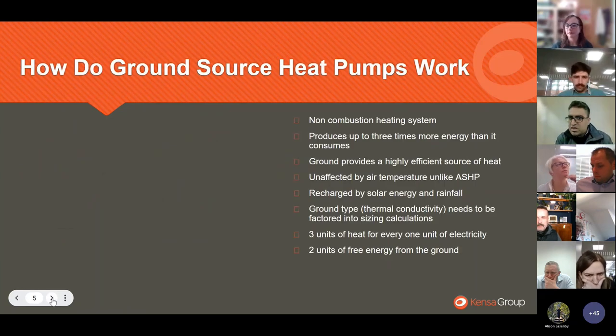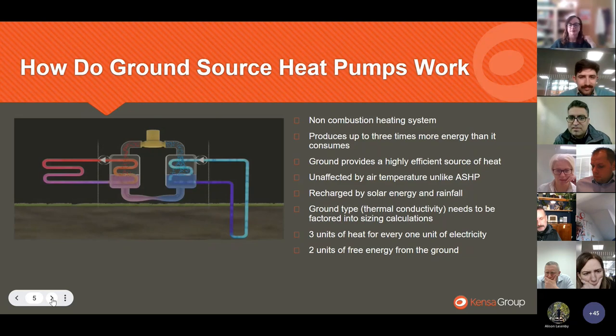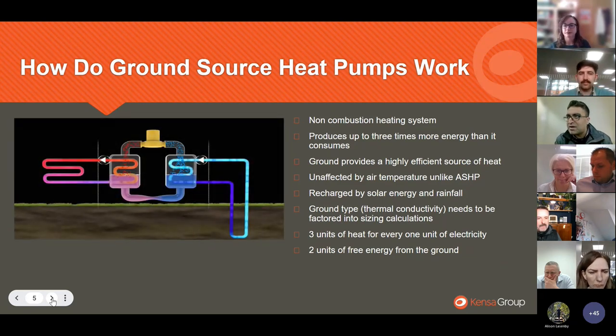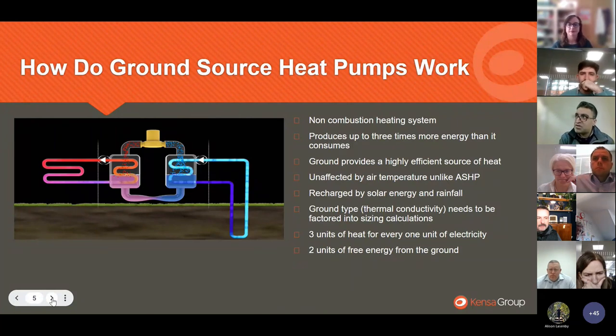So how does a ground source heat pump work? Essentially, you have a white box appliance that collects ambient energy from the ground or from the air - we're talking about ground source specifically, so the ambient energy is collected from the ground and goes into the heat pump. Within the heat pump there's a refrigerant that changes state from liquid to gas, anything from minus 20 and above. That vaporized liquid becomes compressed in a compressor, and as you compress gases, they become hotter.